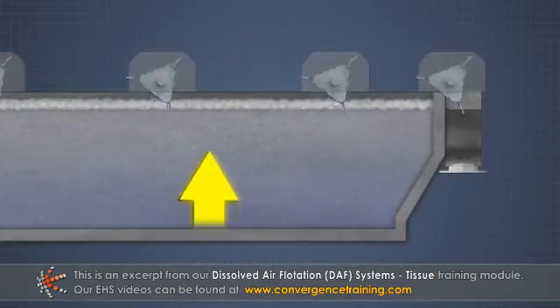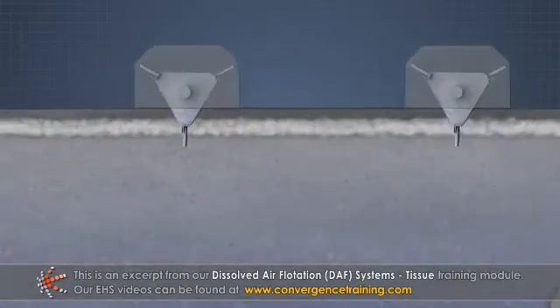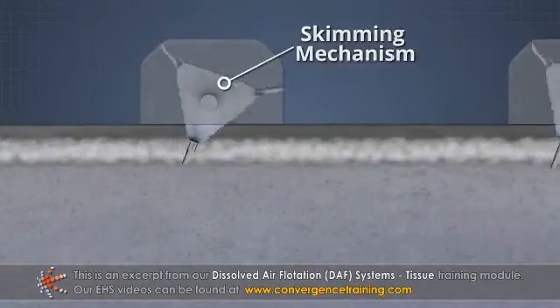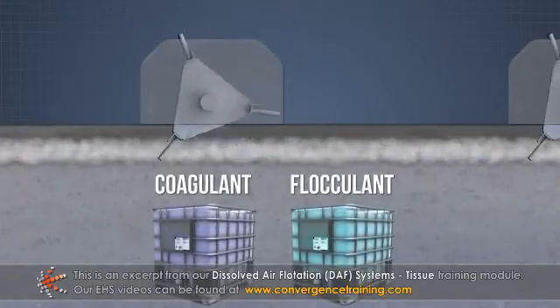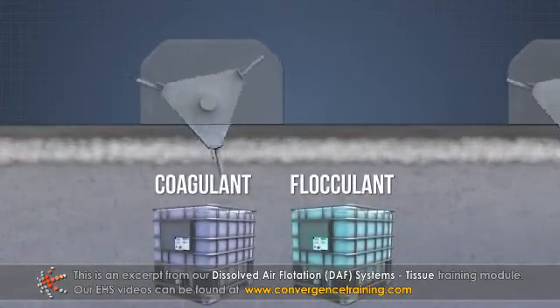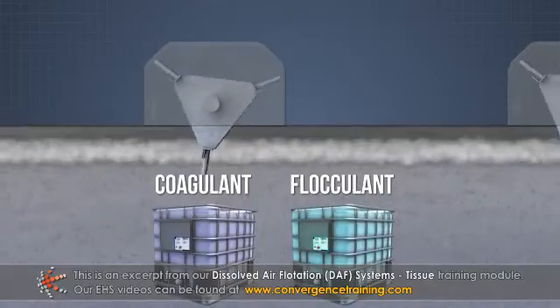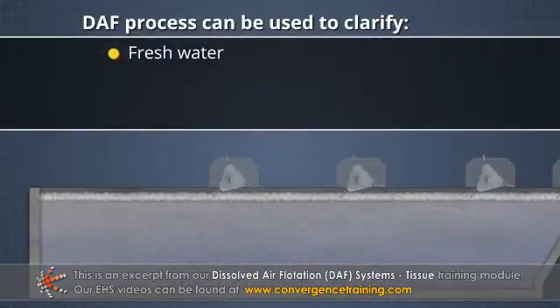The solids float to the surface where they can be removed by a skimming mechanism. Chemicals can be added to the feed water to improve solids removal. The DAF process can be used to clarify fresh water and process water.